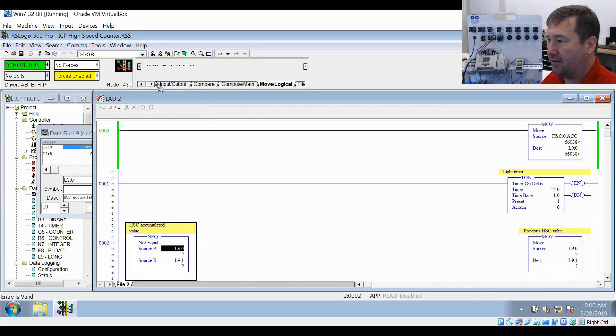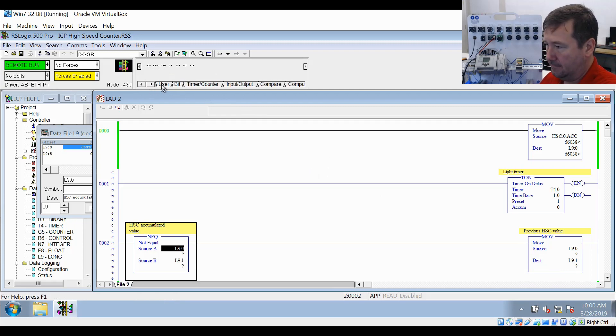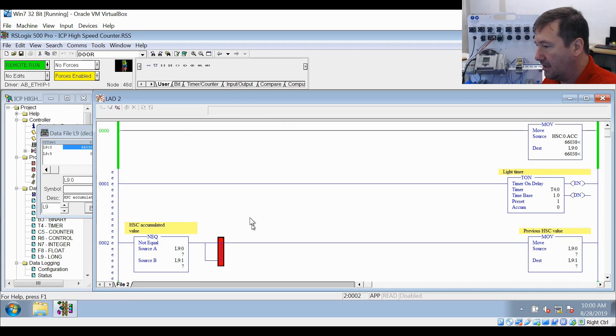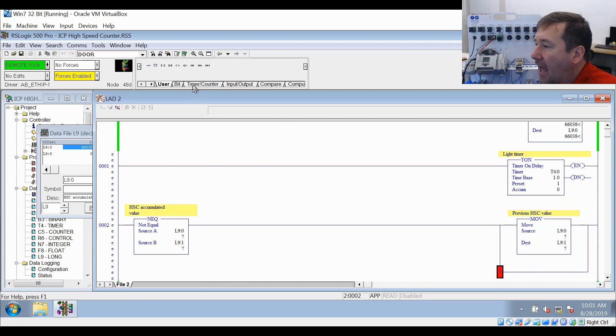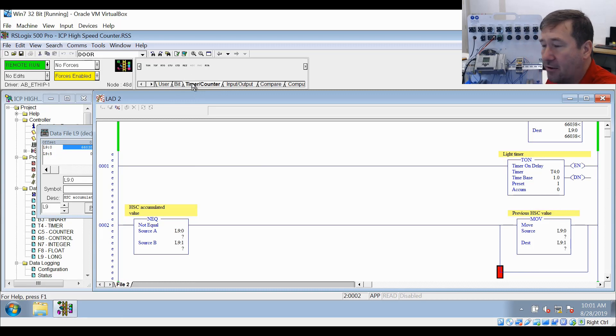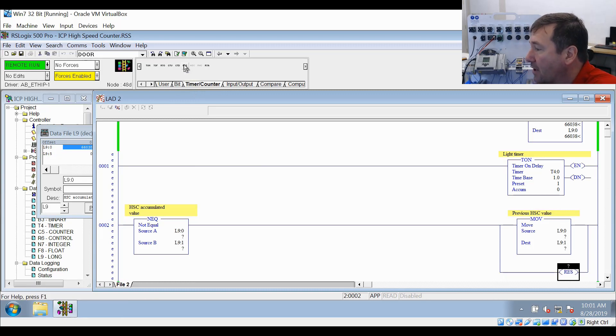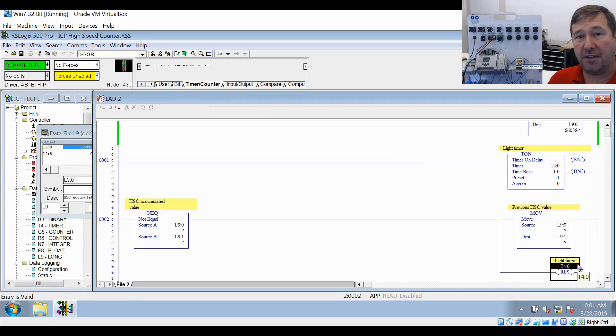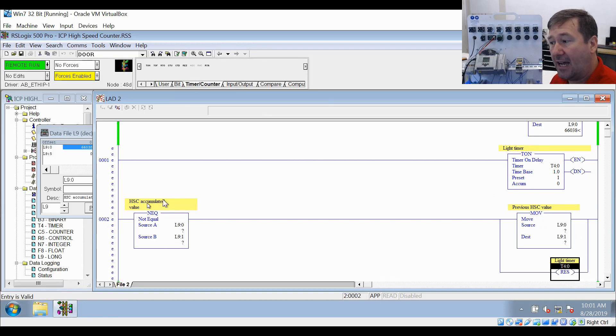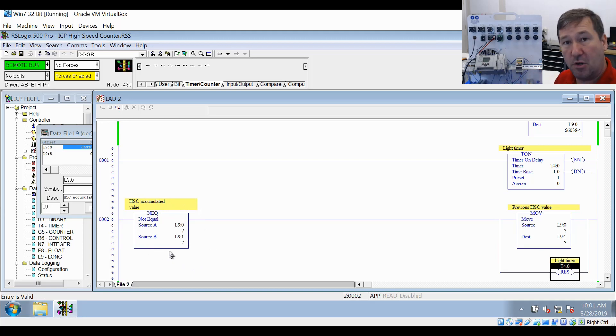Now we're going to add a branch around that move instruction. And here we're going to add a reset instruction for this timer. We go back to our timer and counter tab, hit reset, and we're going to reset T4 colon zero. What this is going to do is any time these are not equal - meaning our high speed counter has moved or position has changed - it's going to reset this timer.